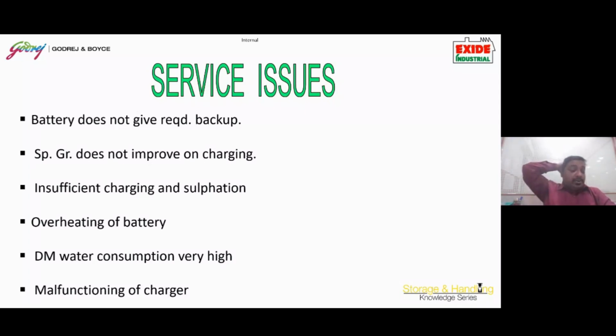DM water consumption also happens because of the above two reasons: one, the temperature is very high; two, there is an internal short; and three, if the internal resistance of the cell has gone high due to prolonged storage or anything, and when we try to charge this with higher current, a lot of heat is generated because of the sulfation, to the extent of I square R. This evolution of heat will evaporate the water content inside the electrolyte.